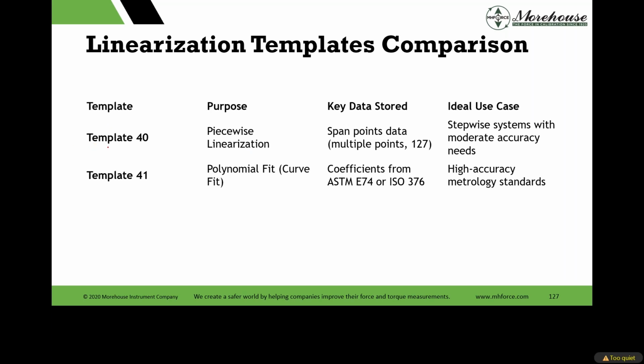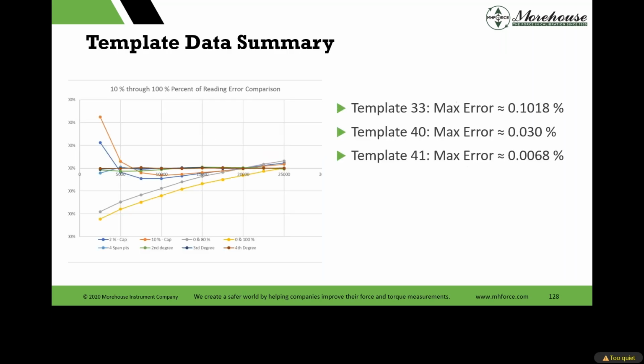So if we look at the higher end templates, which most meters do not do, template 40 and template 41, template 40 allows us to span up to 127 points. So we can really drill down, get all of those 10 data points I showed you. We can drill that down. We can do a lot with that. Template 41 allows for a polynomial equation to be used. Look at this, and we graph it.